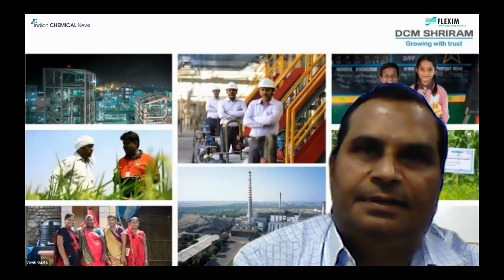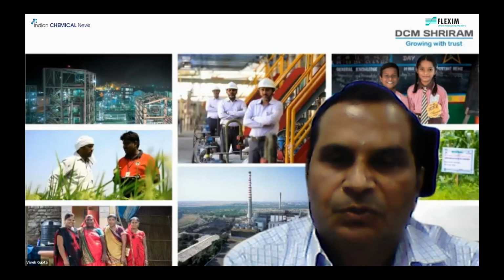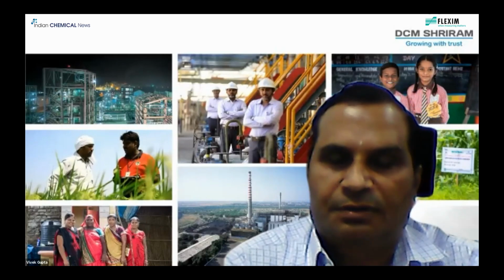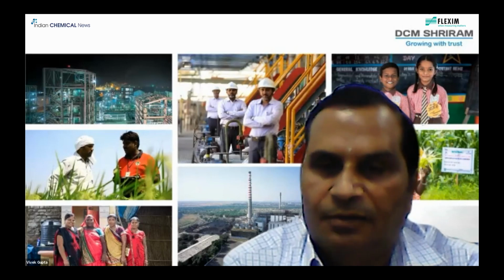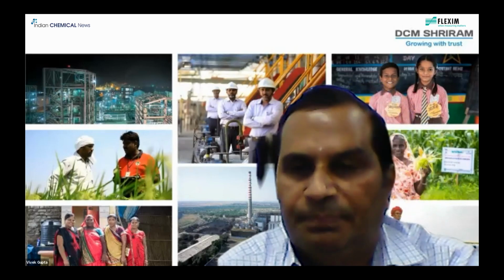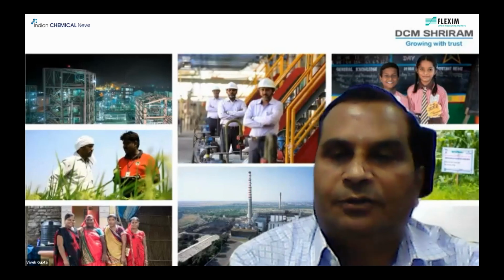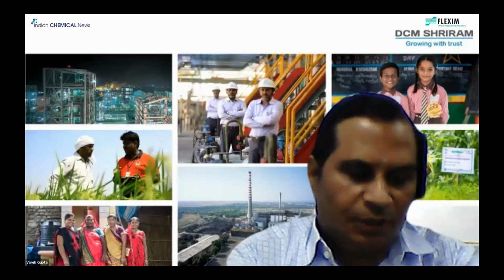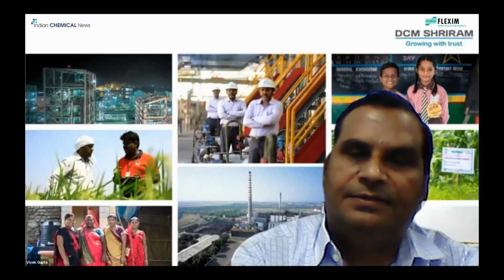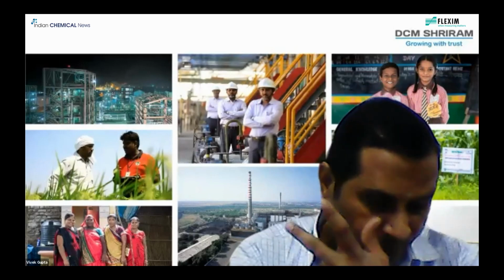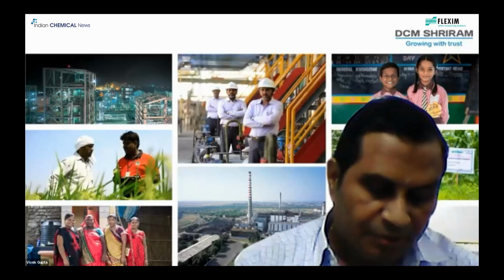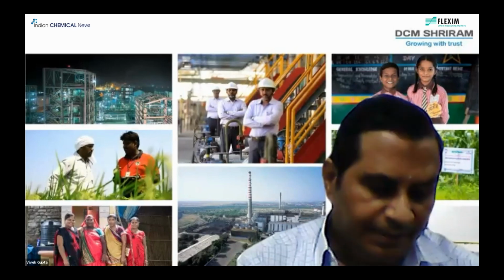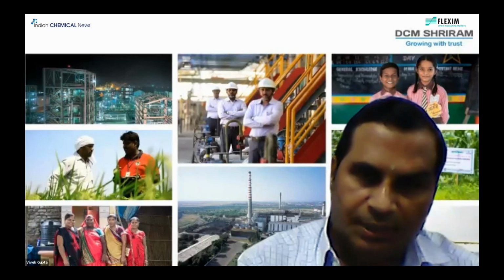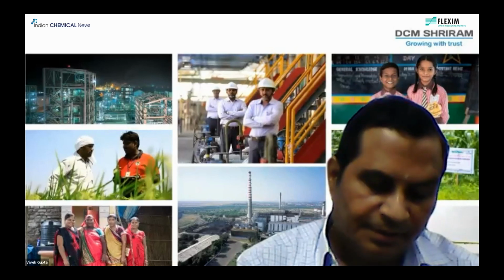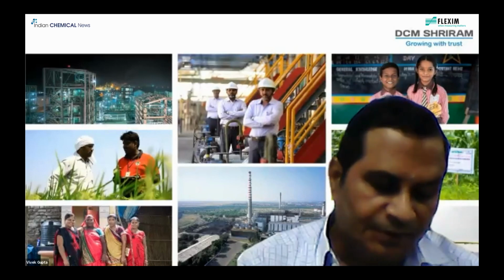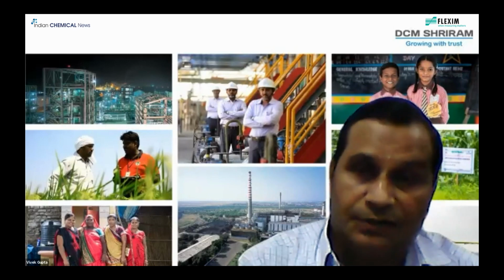So I feel that the key trend is to get a kind of measurement for which we need not stop the plant, we need not do any kind of piping work, we need not do any kind of retrofitting. And what I feel the major trends are the digital signals for the flow meters, the multiple measurement formats, online diagnostics, troubleshooting, remote calibration and configuration, and smart sensors with online alerts.